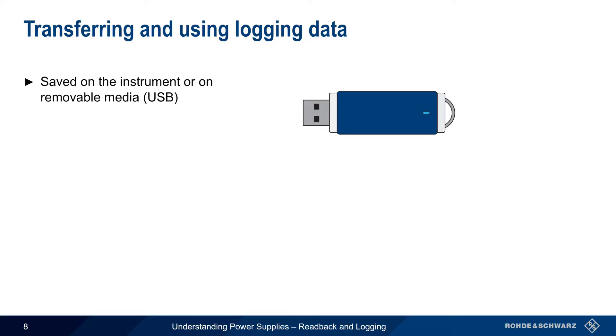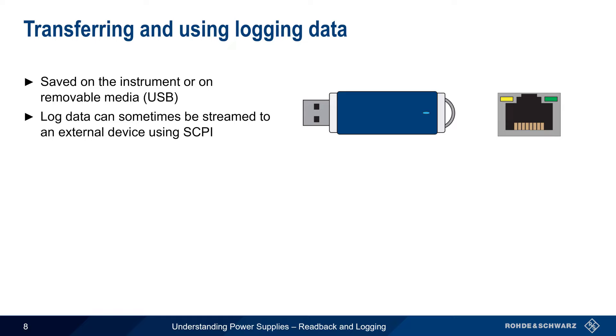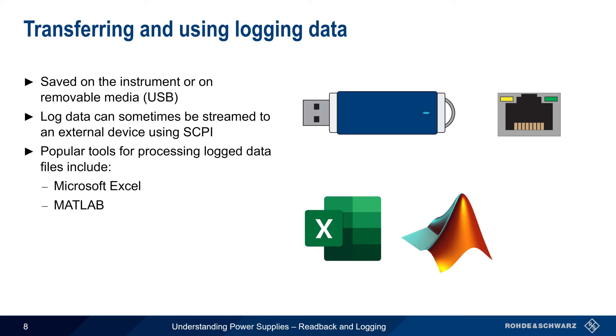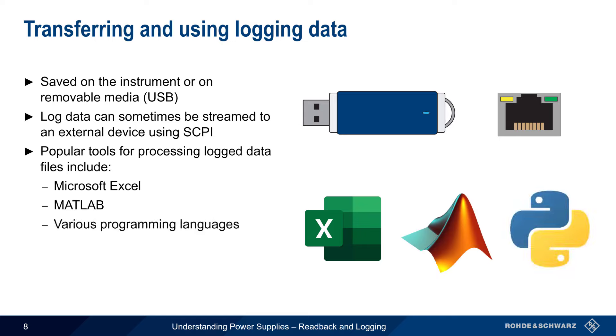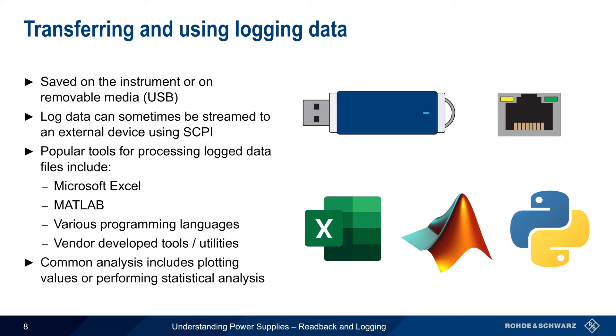Log data is often stored on the instrument itself and/or can be saved to removable media such as a USB drive. In some cases, log data can also be streamed to an external device or computer over a LAN interface using standardized SCPI commands. There are many programs and tools that can be used to process log data, some of the more popular ones being Microsoft Excel, MATLAB, and programming languages such as C or Python. In addition, the manufacturer of the power supply may also provide tools or utilities that work on log data. Plotting log data is one very common task, and statistical or trend analysis is also very commonly performed on these files.